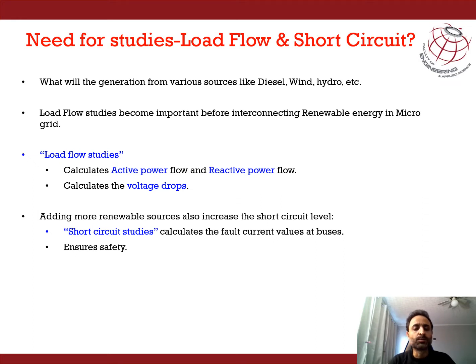By adding more and more renewables to the system, we can make the microgrid unstable, especially with regard to frequency and voltage. The equilibrium or balance of frequency exists when the active power generation by the generators matches the active power consumed by the load. Similarly, the voltage remains stable when the reactive power generated by the generator matches the reactive power consumed by the loads. As a result, an equilibrium is essential for having stability with regard to the active power, the reactive power, as well as the voltage drops.